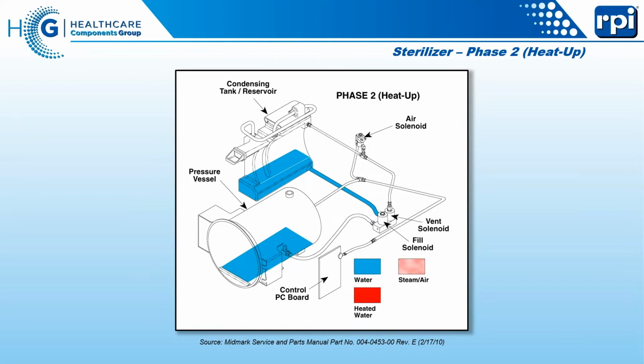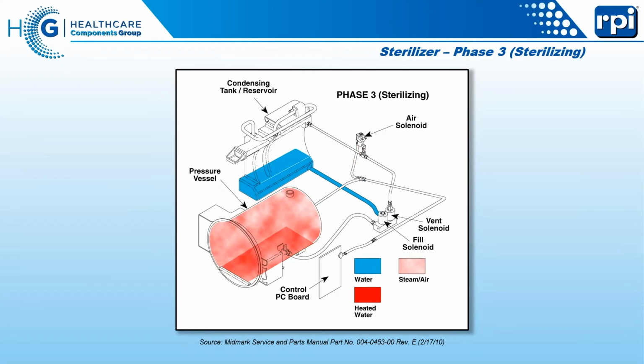So during the heat up phase, we open this valve 3 times, that's the hissing sound you hear, and allow the steam to escape for a short period of time, taking the cold air with it. Okay, so we are still in the heat up phase. So we still have a couple more minutes left till we actually get to sterilizing.